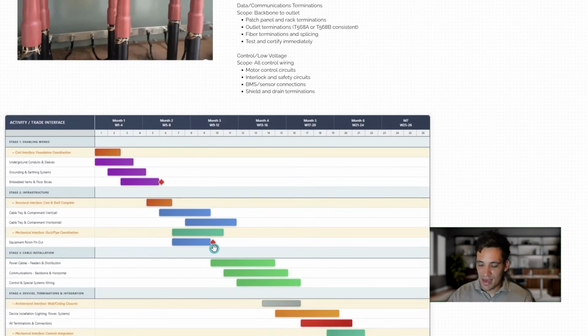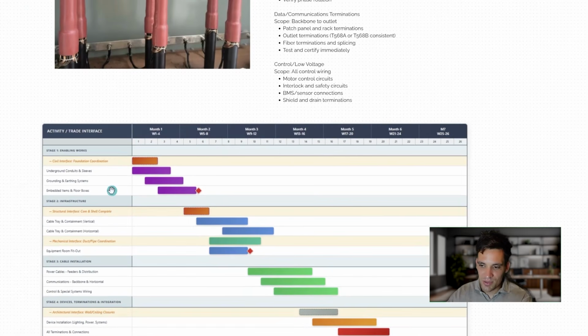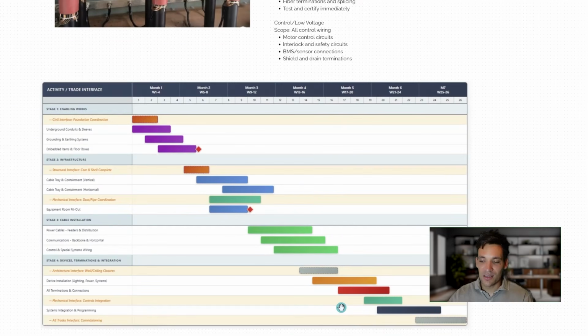We're talking about how this happens in time. Again, we start with civil works and the interface with the civil construction. Once the structure's up, we put up all our cable tray and our main cable tray, and we can fit out our equipment rooms, assuming the procurement's been done on time and we've got our main switchboards. Then once the cable tray's up, we can start running all the cables within the cable tray. Then in parallel with building framing, building construction, building fit out, we can install all our devices and begin terminating our cables to fully complete our electrical system.